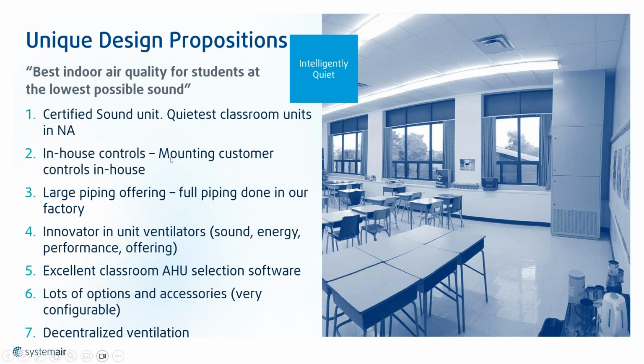In-house controls, right? We mount the controls for you if need be. If your school board is dead set on using Delta controls or Alerton controls or Automated Logic, they could send us their controls and we can mount them in our cabinet and provide wiring diagrams if need be, to help make sure that the project management on the job comes in nice and clean. Large piping offering, as I mentioned before: we have Y strainers, manual circuit balancing valves, control valves, etc. Two-way, three-way. You can even do a stainless steel offering if need be.